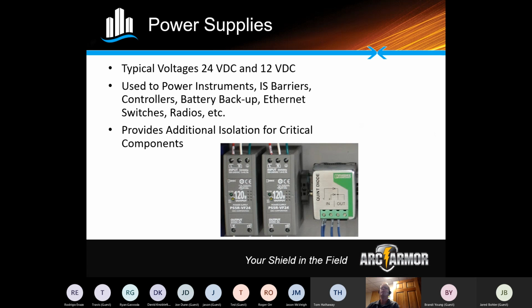All right, moving on. Power supplies. What are power supplies? What do they look like? What are they used for? Oops, sorry about that. So power supplies, also used for isolation. They are provided in panels to go from a 120 VAC or AC power to DC, so direct current. So it's not alternating anymore. And your typical voltages that you're going to see in a panel are 24 volts and or 12 volts. These are used to power instruments.